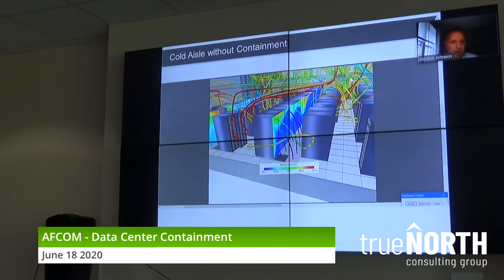Now, you might not be able to see it that well, but this data center has a translucent drop ceiling. So it's got ceiling grills. All that hot air should be going up into the ceiling, back to the CRACs, and it does eventually, a lot of it, but again, what's happening is the hot air is coming in the cold aisles, it's heating up your equipment. In addition, cold air is blowing, and it might be hard to see, but in the back of that main aisle, it's blowing right out of the cold aisle up into your drop ceiling. So you've got net recirculation air and also bypass air going on in this data center.